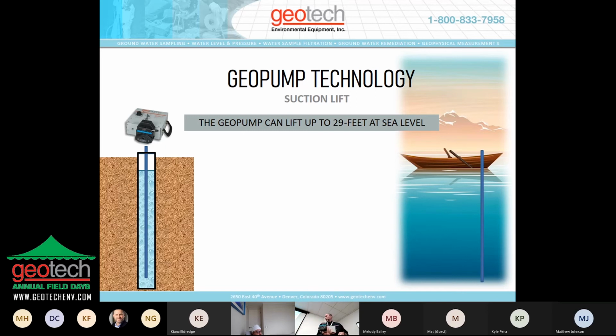And so for the rest of the crowd here. When we open this up, we can see there's rollers. It uses a flexible tubing of a particular size, depending on what you're dealing with. And these rollers will squeeze the tubing and roll it forward. That pushes an air pocket forward, which creates a negative pressure behind the roller. That negative pressure, i.e. vacuum, is what's pulling the sample up the tube.